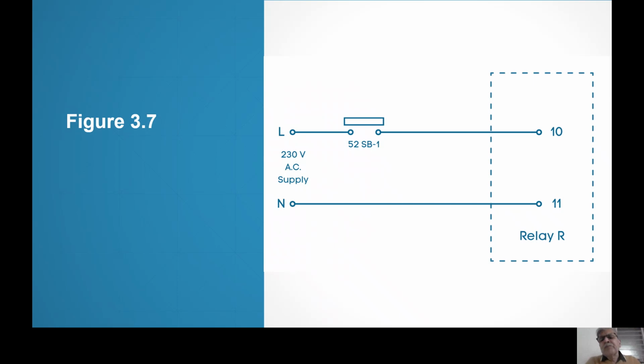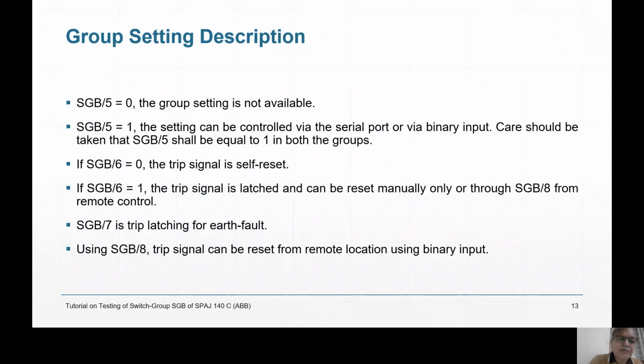And you see, you can use the auxiliary switch of the sectionalizing breaker to change the setting, as you have been doing in earlier cases, right? So that can be done. If SGB5 is equal to 0, then this group setting facility is not available. But if you make SGB5 equal to 1, then you have to give a binary input. Then you can change the setting from setting number 1, main setting, to secondary setting. So for changing from main setting to secondary setting, you have to make SGB5 equal to 1. It's a soft switch, and you have to give the binary input.